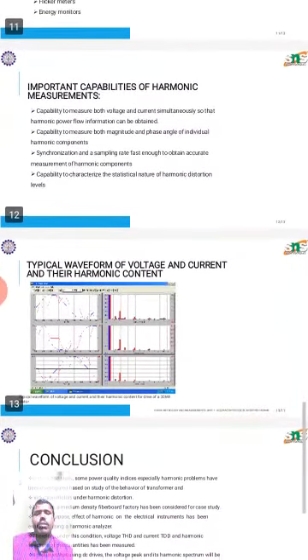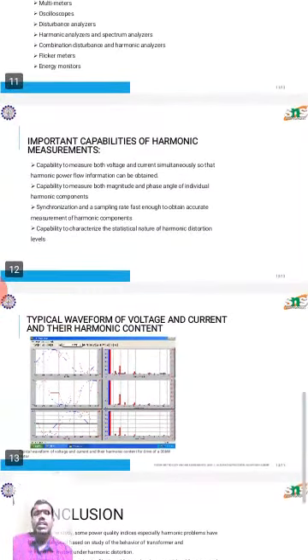Next one, typical waveforms of voltage and current and their harmonic effects are shown. For the sake of harmonic analysis, the MDF factory has been selected as a case study. This factory has many DC and induction motors, electrical drives with switching devices and transformers. The AC to DC drives used in this factory produce and inject a significant value of harmonic distortion in voltage and current waveforms.